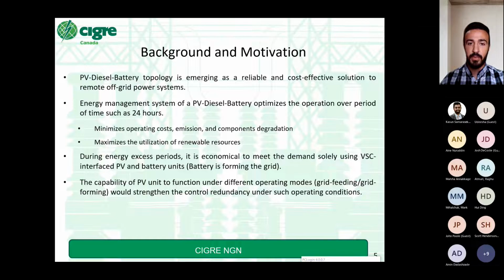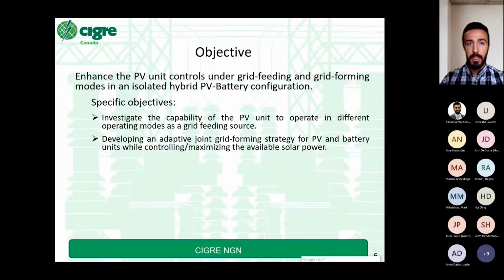During energy excess periods, it can be noted that it's economical to meet the demand solely using a VSC interfaced PV and battery units, for which case the battery is going to be forming the grid. Therefore, the capability of the PV unit to function under different operating modes, such as grid feeding and grid forming, would strengthen the control redundancy under such operating conditions.